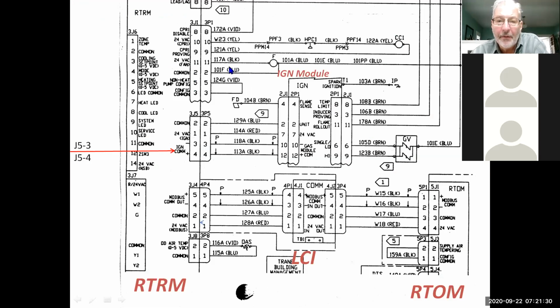If you look at the wiring schematic on these boards, here's the ignition modules. Here's our LCI, which is our LonTalk communication interface, if we had that in the system. Again, here's our Modbus. So there's red and blue for power, and there's the 2 black wires for communication. There's our communication to the options module. So if we go from the Modbus to the options module, again, Modbus follows through. So the 2 black wires, the blue and the red, and it's always gonna be the same on all the Modbus communications. Here's our J5, which goes to the ignition module, or our J4, which goes to the communication bus, to the options module, and then eventually it goes back to the economizer. So it all kind of daisy chains through the system.